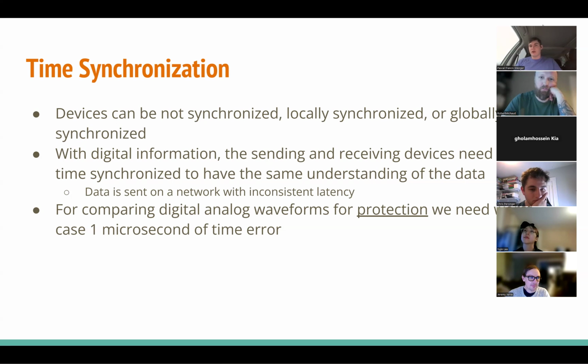You've probably seen this in your car clock, that if you leave it without adjusting it, over time it'll move into the future or past. For normal use, you'll only notice it once it gets off by a minute or so. But when we're talking about substation uses and time synchronization, especially comparing waveforms, we're talking about accuracy to about 1 microsecond. That amount of drift can take place over a very short time frame. In your car, it takes a year to get off by a minute, but in a substation, an IED can drift a microsecond in as little as 2 to 10 seconds.